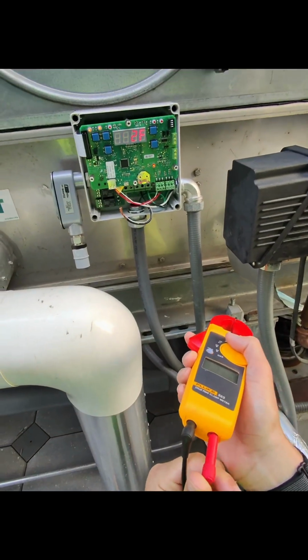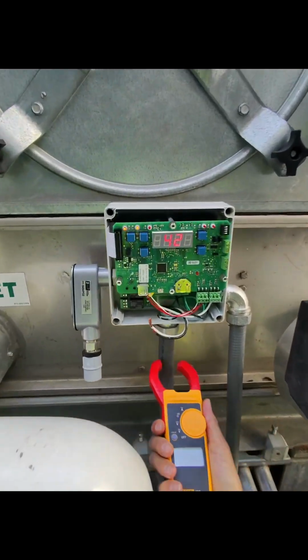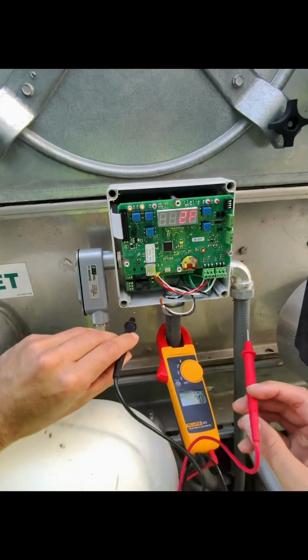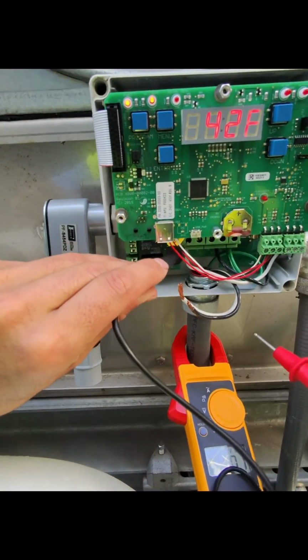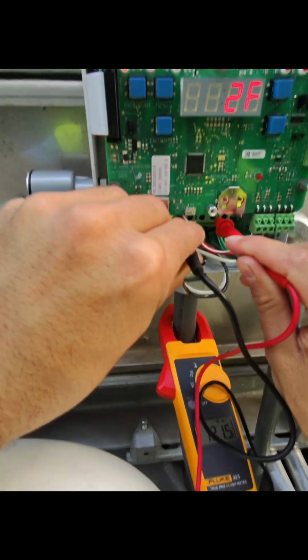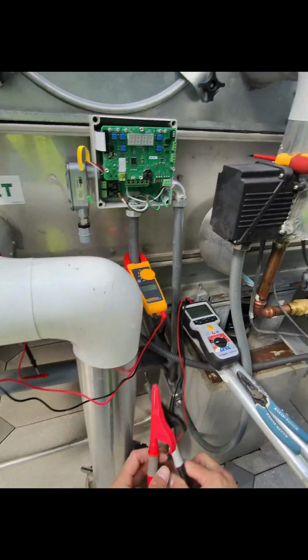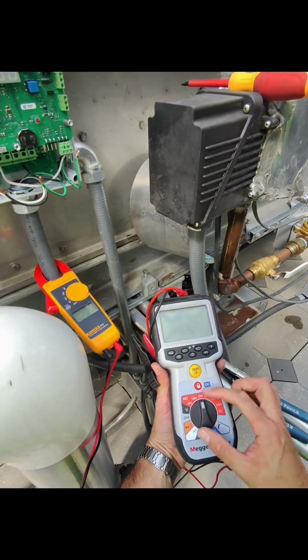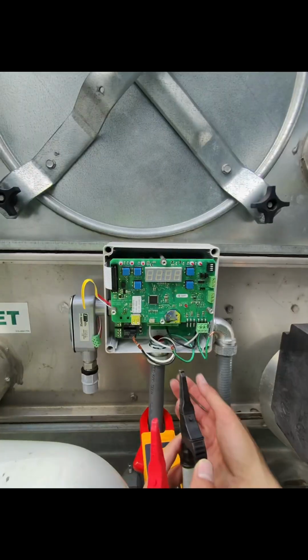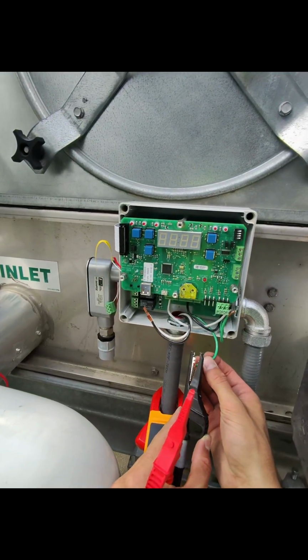Next up, I'm going to measure the voltage of the panel to make sure it's within spec and correlates with the connected heat trace cable, which is either rated for 120 volts or 208 to 277 volts. Next, I'll be doing a Megger test. This is required by the manufacturer of the heat trace cable, Chromalox.